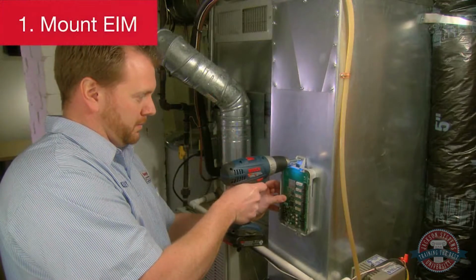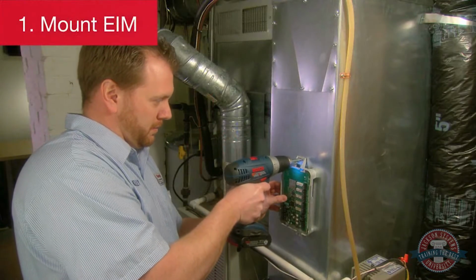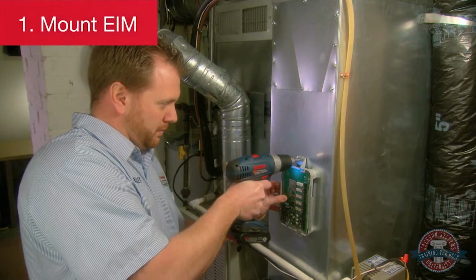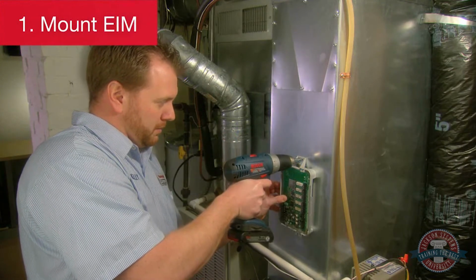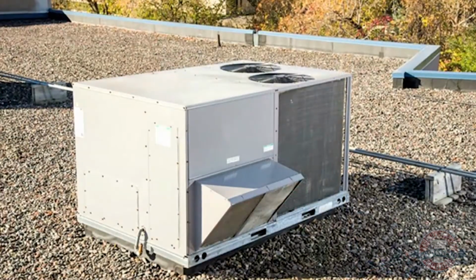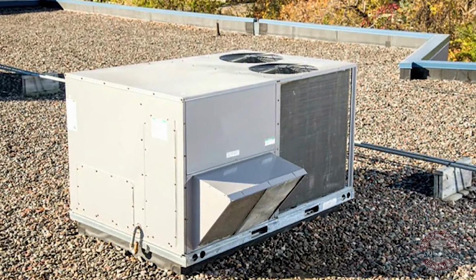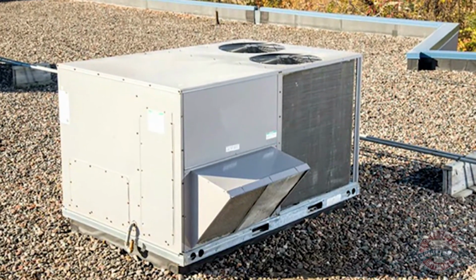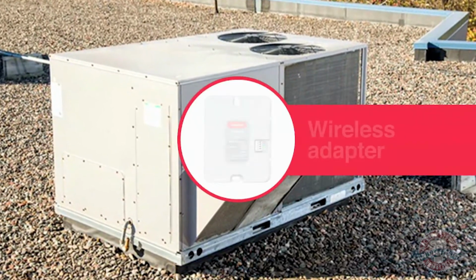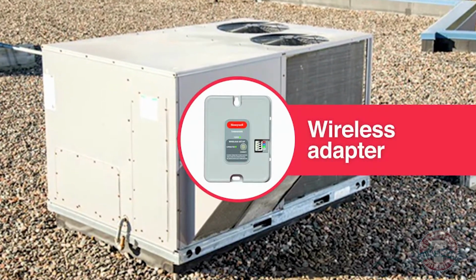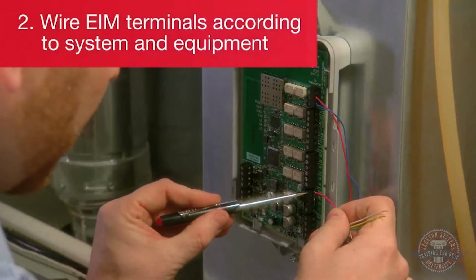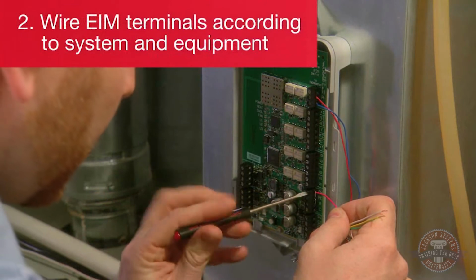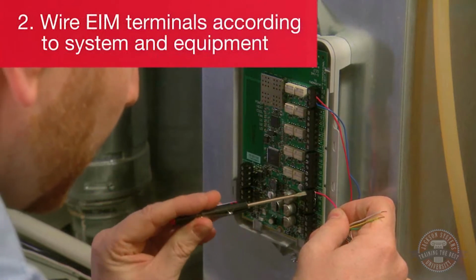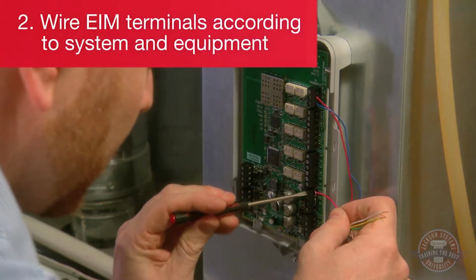First, mount the EIM near the equipment or on the equipment itself. Use screws and anchors as appropriate for the mounting surface. If you're mounting an EIM inside a metal cabinet, such as a commercial rooftop unit, we recommend using a wireless adapter for extended range. Wire applicable equipment to the corresponding EIM terminals based on the designations listed in your install guide.